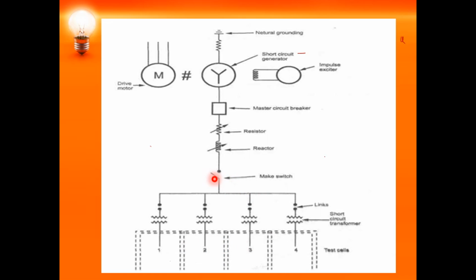So what you have to do is close the make switch. So the make switch is closed. Now, for the circuit breaker under test, once the fault current flows, what should happen? The circuit breaker under test has to open its contacts. In case it fails to open the contacts, which one has to open? The master circuit breaker has to open the contacts. And once it is opened, what will happen? The impulse exciter which was applied now has to be turned off.